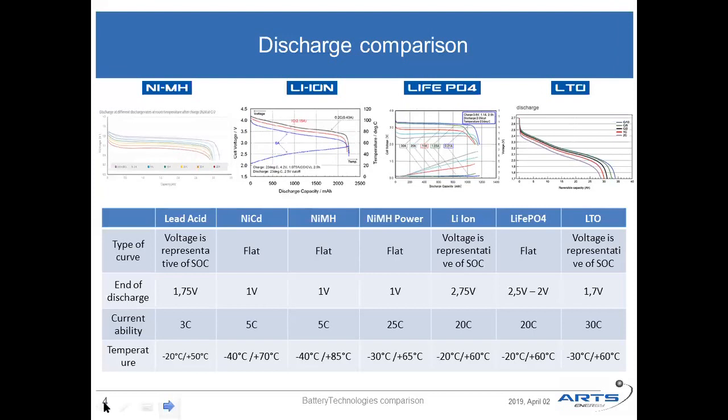For the temperature in discharge, there are no major differences between technologies. The only point to keep in mind is that nickel cadmium has a particular and excellent behavior in power at very low temperature. This is the main reason why nickel cadmium is still used today.